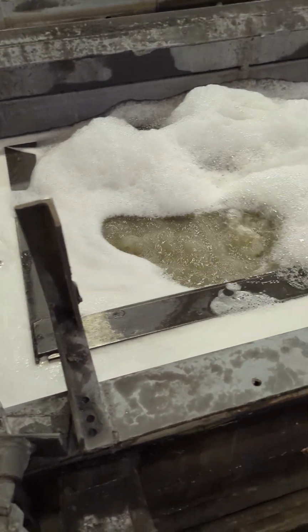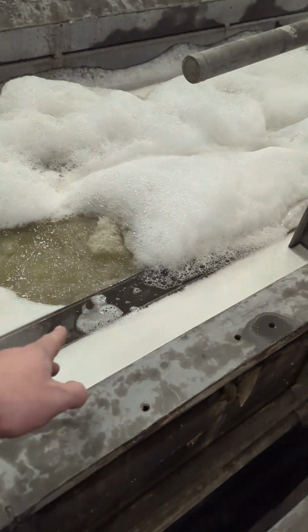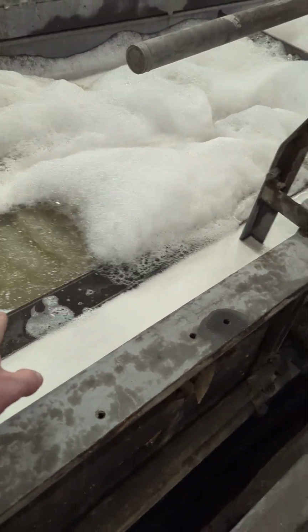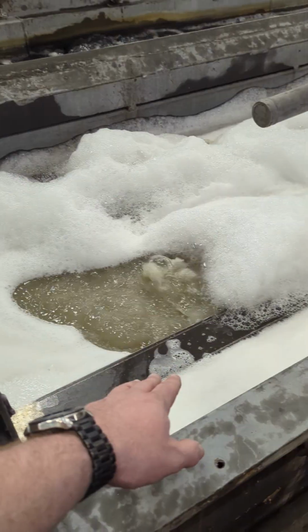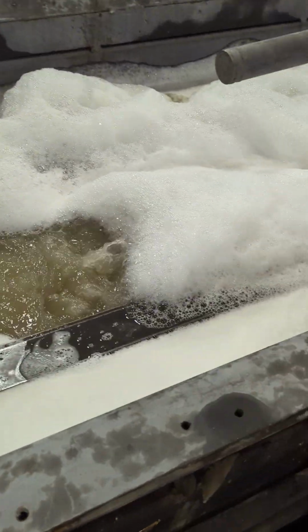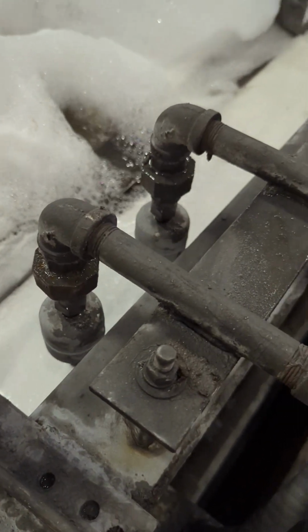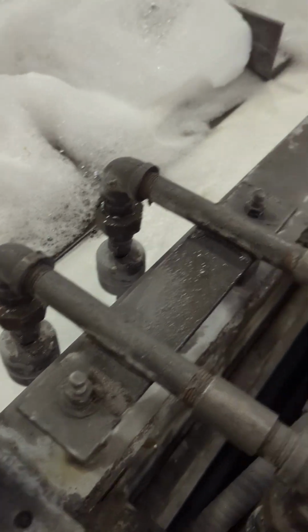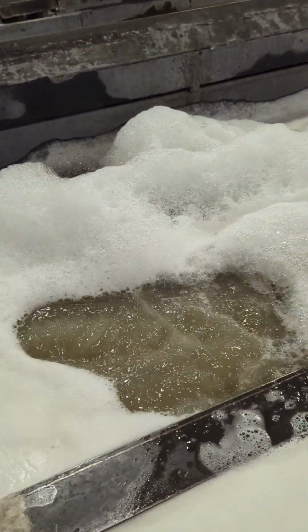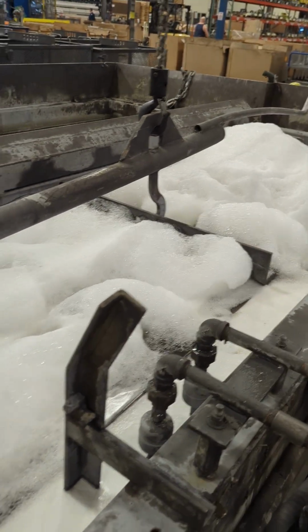The tank was here. We used to have over-the-tank heaters right here, but they would keep getting broken by these big carts, or the water level would run low and they would burn up. But we have an autofill system, 2 floats tied in series, turn on some solenoids over there and fill it up. And a sparger air agitation system at the bottom.